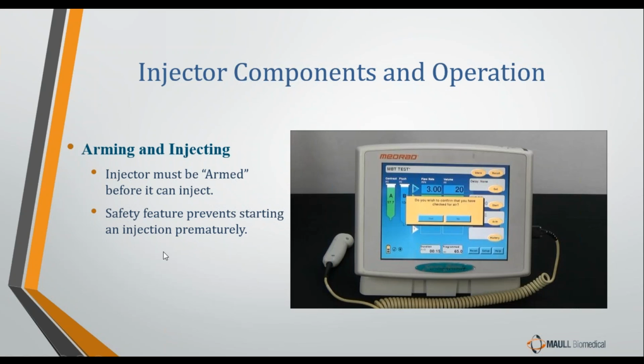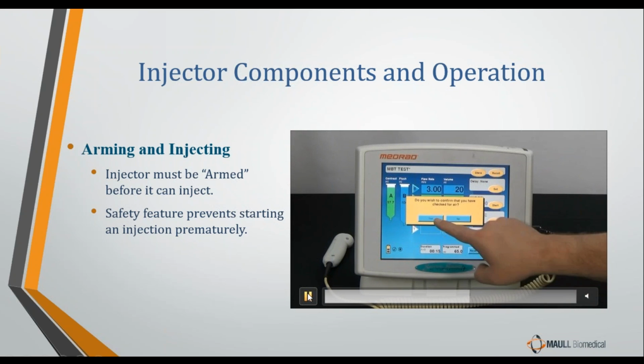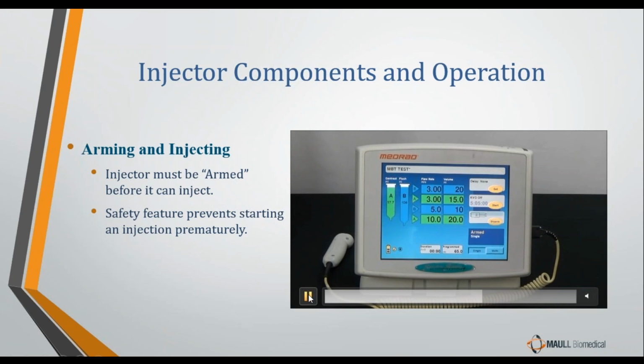It's asking the operator, at this point we're getting ready, we're arming the injector because we want to inject fluid into the patient. So as soon as we hit this arm button, the message pops up, do you wish to confirm you have checked for air? This is the operator telling the machine, yes, there is no air in the syringe, and there is no air in the connector tubing. So as soon as the operator clicks yes, there I am, now we are armed.